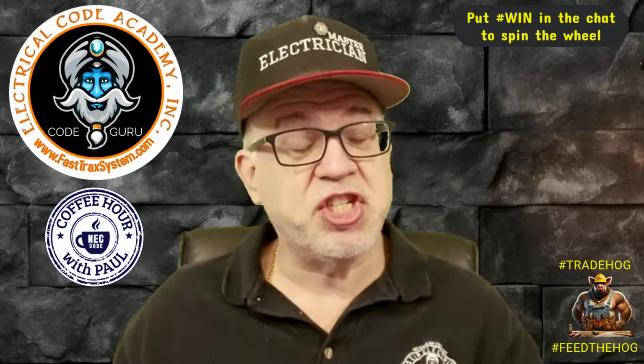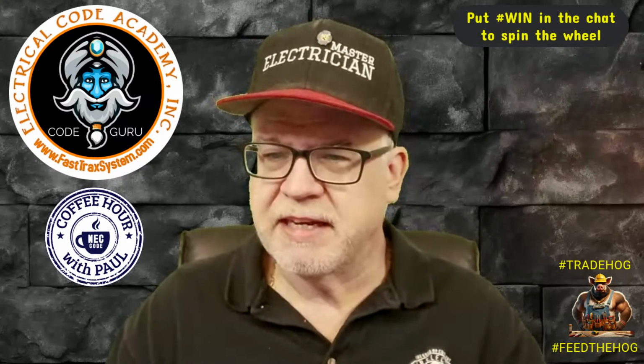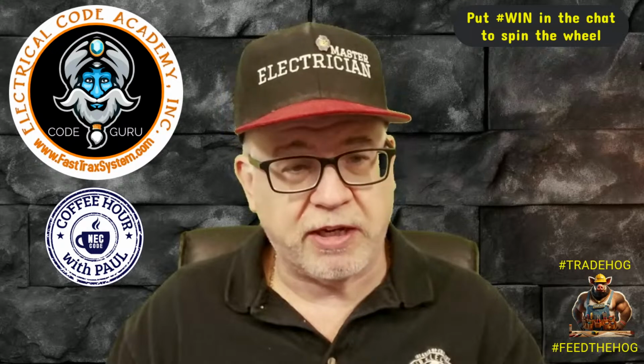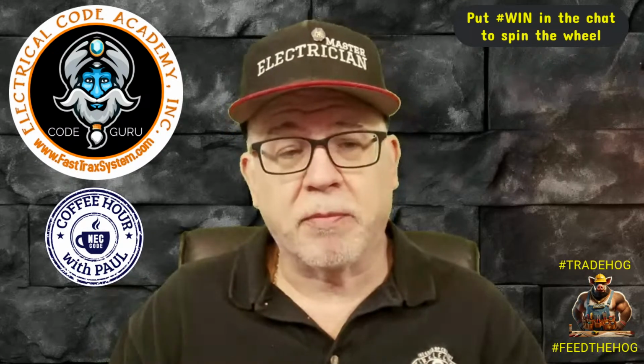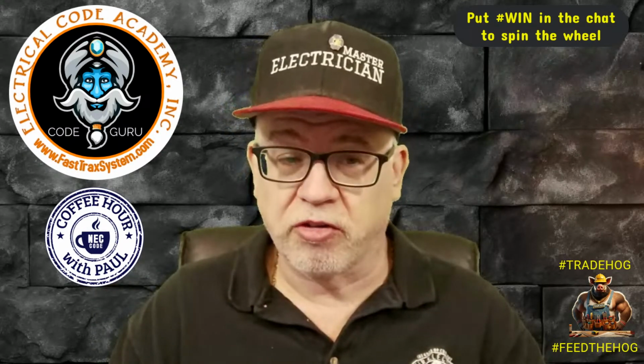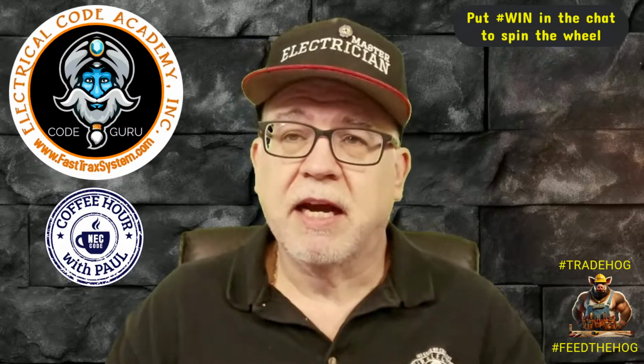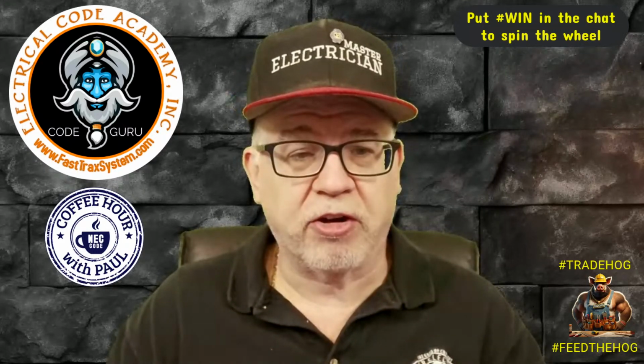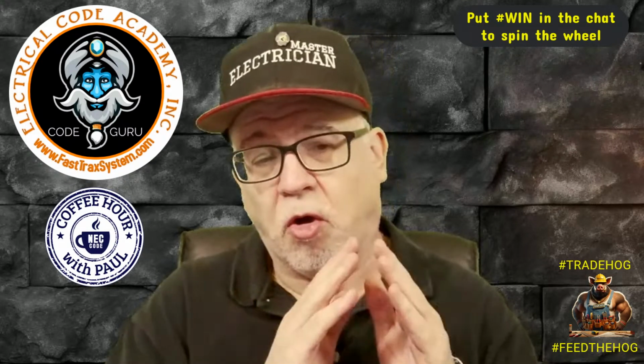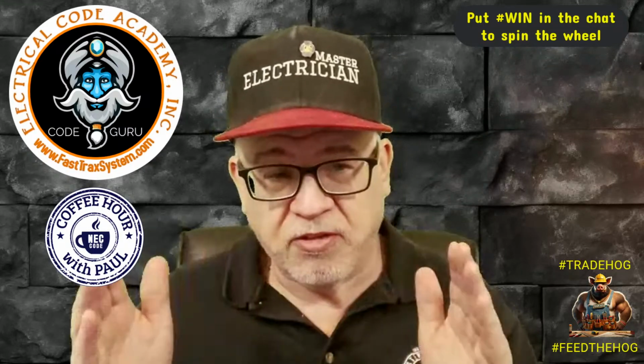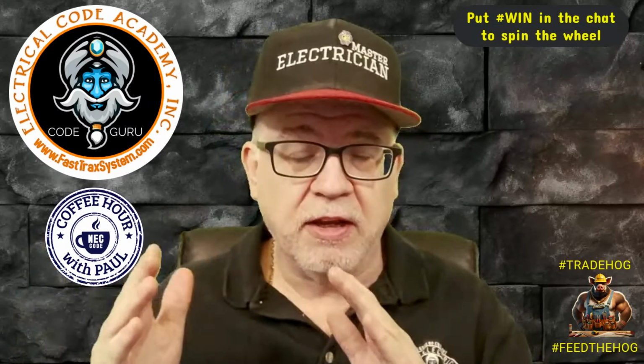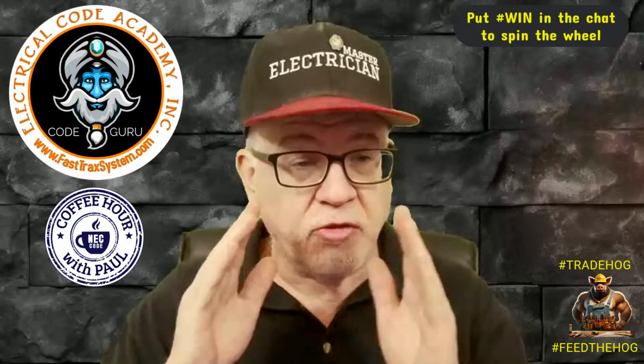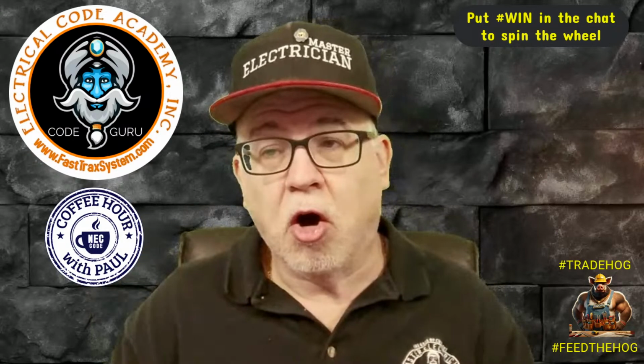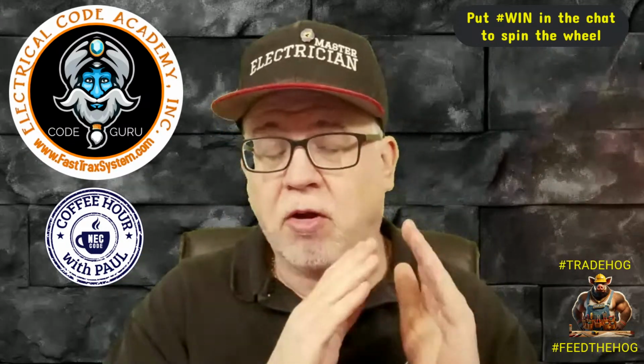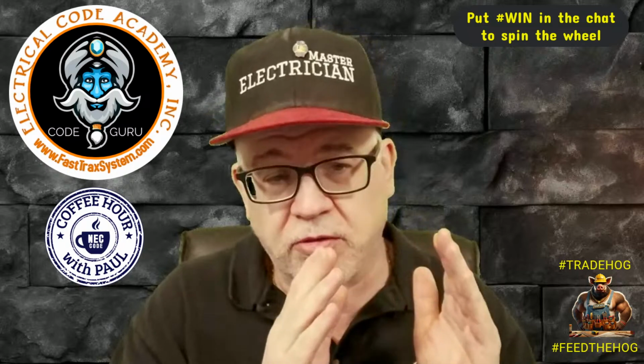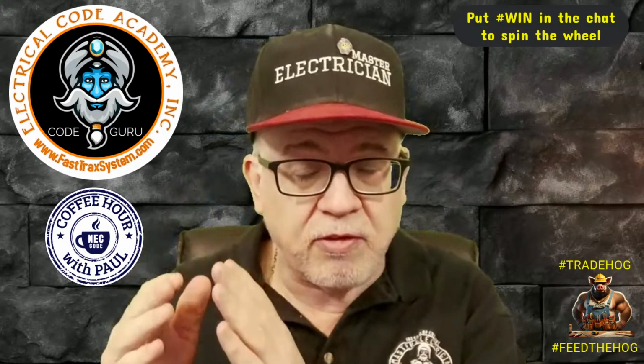So it's now 310.10(G), and basically it talks about your characteristics. So if you're going to parallel feeders, they have to be 1/0 and larger, okay? You have to follow all of the rules, the characteristics, okay? So if you had A, B, and C, and multiple sets, let's say 2 sets, 2 A's, 2 B's, 2 C's, all the A's have to be the same conductive material, all the same length, all the same characteristics, same for the B's and same for the C's.